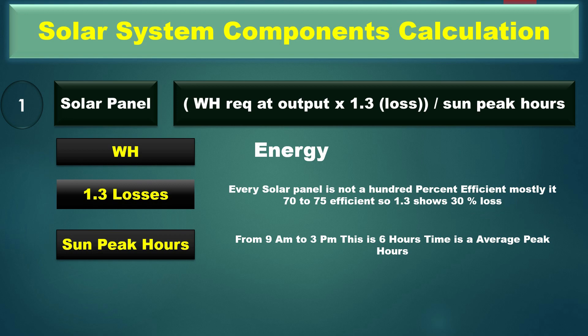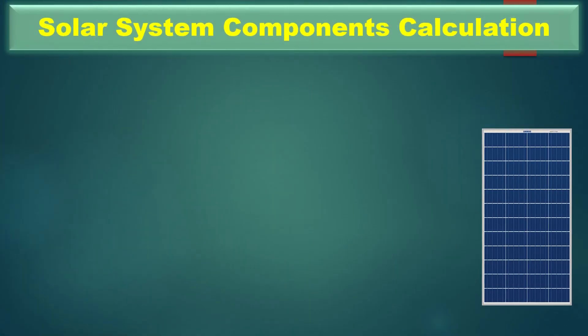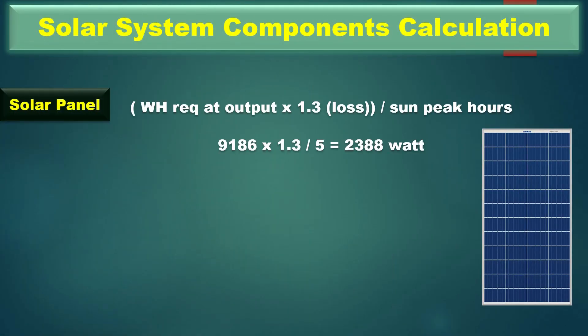Sun peak hours means from 9 a.m. to 3 p.m. This 6-hour window is the average peak hour period every year, but we can also use 5 hours due to sun intensity variations. Putting the values into the solar formula: 9186 multiplied by 1.3, divided by 5 — the answer is 2388 watts.